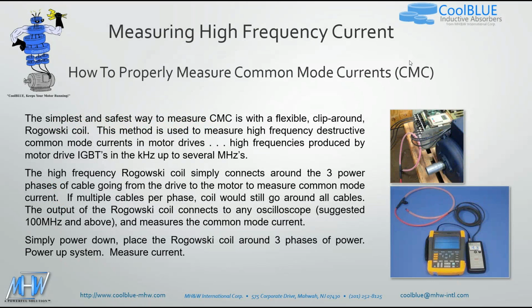The simplest and safest way to measure these common mode currents is with a flexible clip-around Rogowski coil, as shown here. This method is used to measure high-frequency destructive common mode currents in motor drives. These frequencies are in the kilohertz up to several megahertz. This is really the only method to be able to measure these kilohertz and megahertz frequencies.